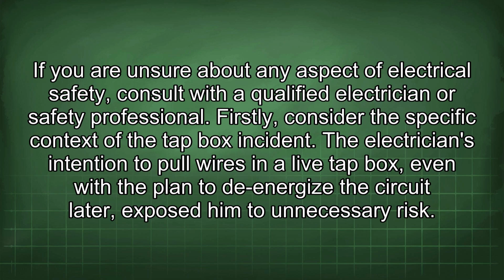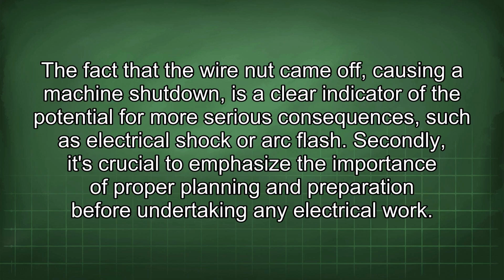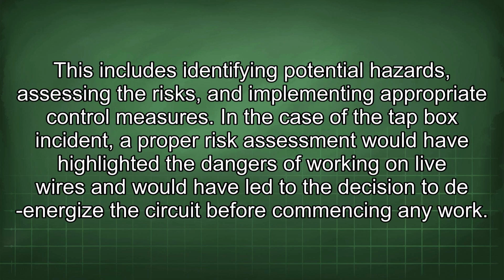exposed him to unnecessary risk. The fact that the wire nut came off, causing a machine shutdown, is a clear indicator of the potential for more serious consequences such as electrical shock or arc flash. Secondly, it's crucial to emphasize the importance of proper planning and preparation before undertaking any electrical work. This includes identifying potential hazards, assessing the risks, and implementing appropriate control measures. In the case of the tap box incident, a proper risk assessment would have highlighted the dangers of working on live wires and would have led to the decision to de-energize the circuit before commencing any work.